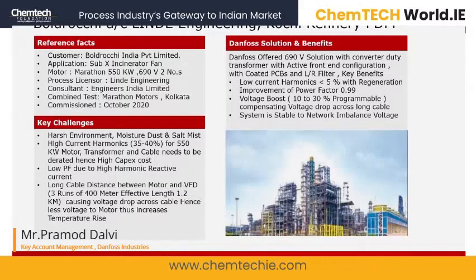The key challenge in this project is definitely the environment, where you see moisture, dust and salt mist. And since the ratings are very high, like 550 kilowatt and in that range, we have very high input harmonics, which will cause high transformer and cable derating, which will always cost more in capex. So this is one very big issue when you are operating with VFD and a higher kilowatt motor: the high input current harmonics. And because of this high harmonic reactive current, your power factor also becomes low. And due to these 2 major reasons, your efficiency comes down.